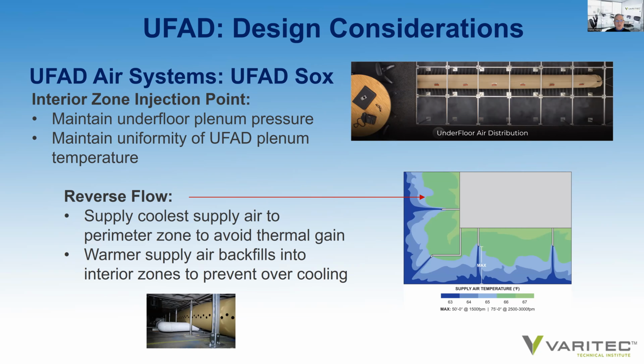And Air Fixture themselves have actually taken this even further and have demonstrated, and you can use sheet metal ducts as well, that you can do higher velocity discharge air. And I don't remember if it was 2,000 feet per minute or 3,000 feet per minute. Doesn't necessarily provide the sound challenge that you might consider. And if you inject that air at high velocity to the perimeter, you can overcome the overcooling of interior zones by providing an adequate amount of properly conditioned supply air to the perimeter when you're in peak summer cooling condition.